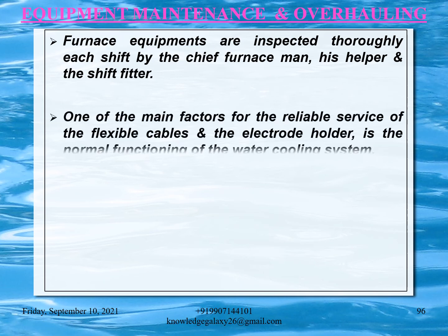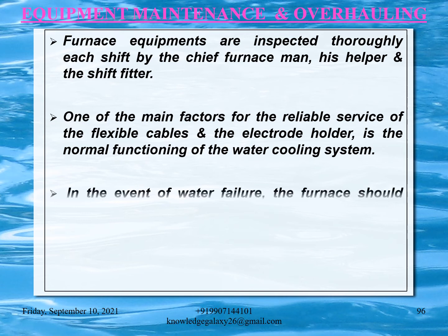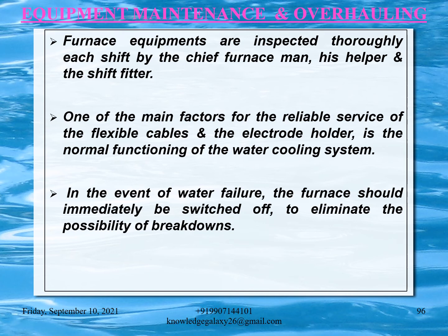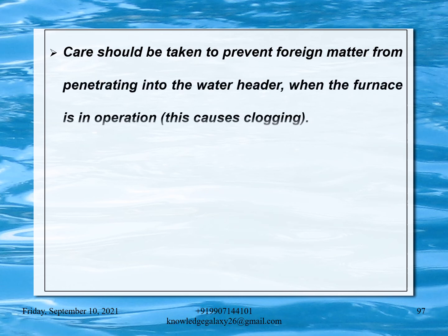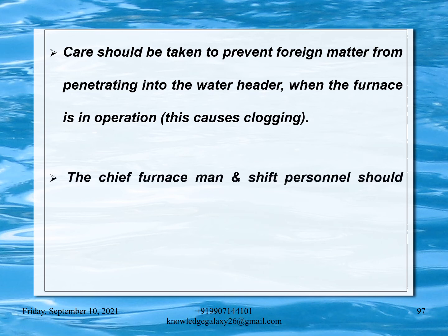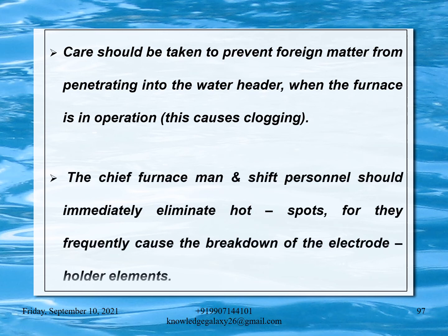One of the main factors for the reliable service of the flexible cables and the electrode holder is the normal functioning of the water cooling system. In the event of water failure, the furnace should immediately be switched off to eliminate the possibility of breakdowns. Care should be taken to prevent foreign matter from penetrating into the water header when the furnace is in operation, because this causes clogging. The chief furnace man and shift personnel should immediately eliminate hot spots, for they frequently cause the breakdown of the electrode holder elements.